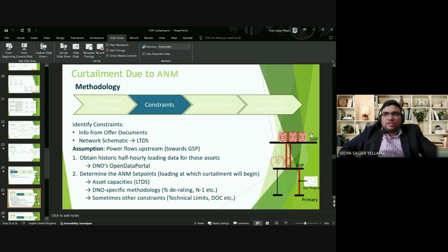This is the GSP, where there are 275 or 400 kV by 132 kV transformers. This is the grid supply point, GSP. After that, there are some lines that lead to the BSP as well. BSP means bulk supply point or grid. And from the grid, there is a line leading to a primary, and in between, on this line, this project is connected.